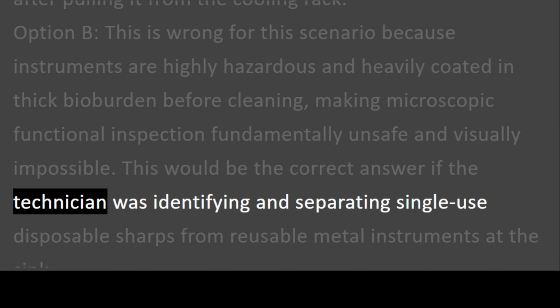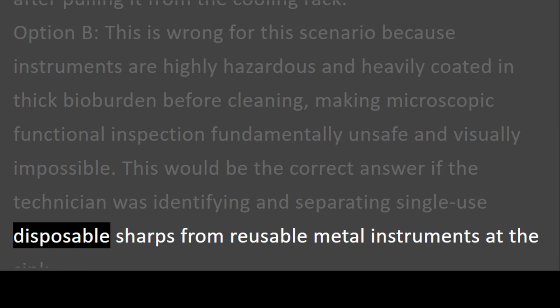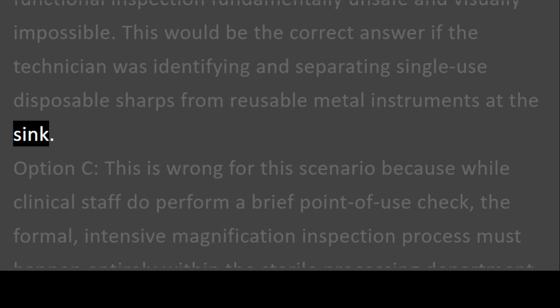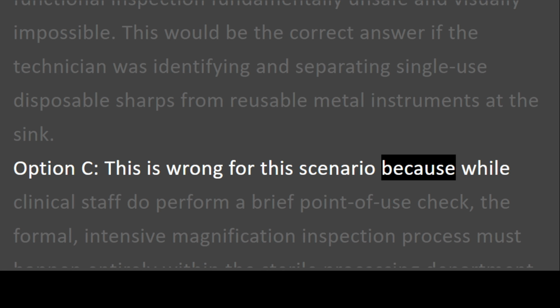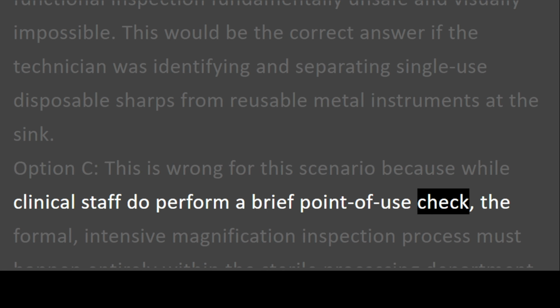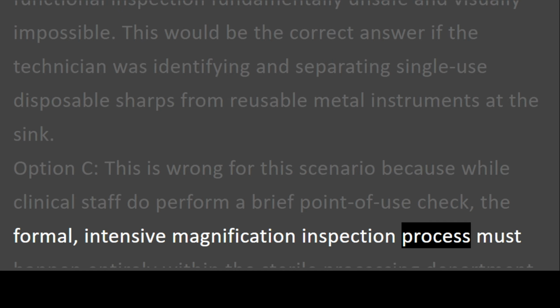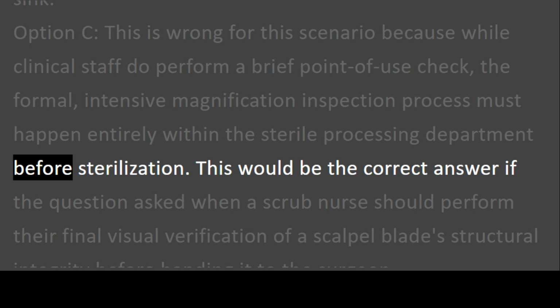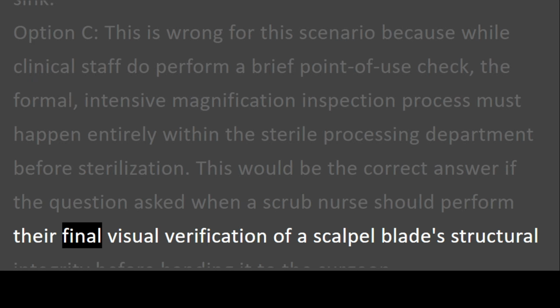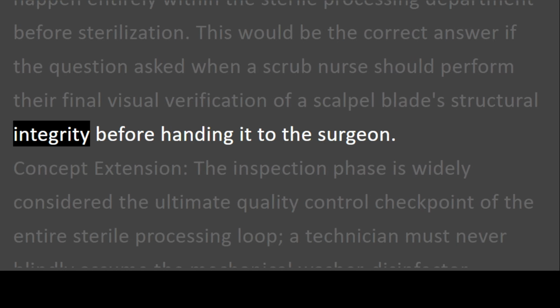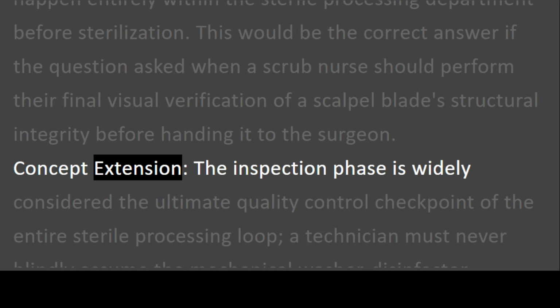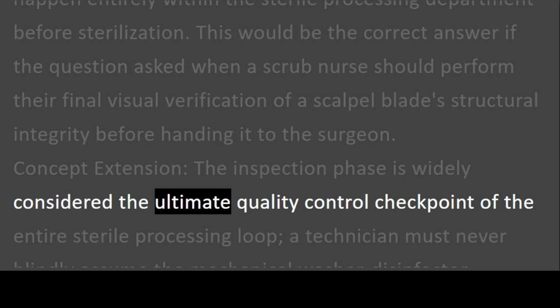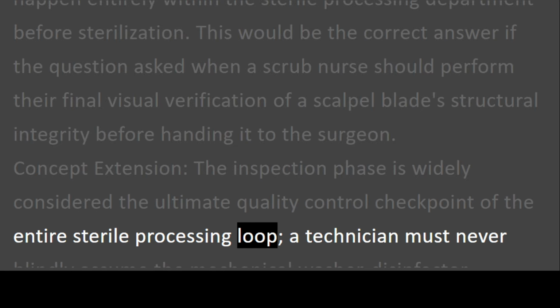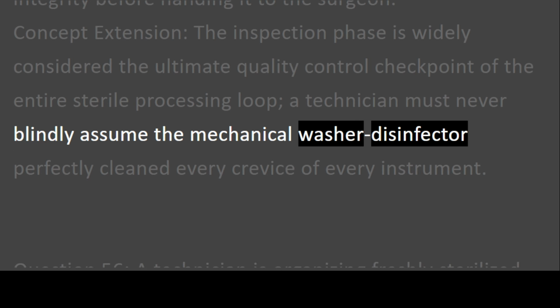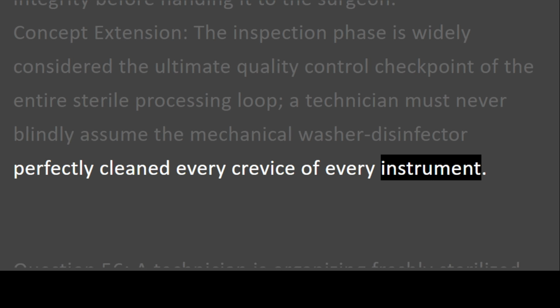This would be the correct answer if the technician was identifying and separating single-use disposable sharps from reusable metal instruments at the sink. Option C. This is wrong for this scenario because while clinical staff do perform a brief point-of-use check, the formal, intensive magnification inspection process must happen entirely within the sterile processing department before sterilization. This would be the correct answer if the question asked when a scrub nurse should perform their final visual verification of a scalpel blade's structural integrity before handing it to the surgeon. Concept extension. The inspection phase is widely considered the ultimate quality control checkpoint of the entire sterile processing loop. A technician must never blindly assume the mechanical washer disinfector perfectly cleaned every crevice of every instrument.